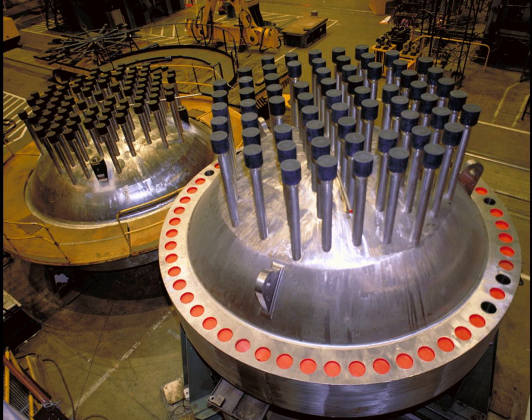The high-temperature water coolant with boric acid dissolved in it is corrosive to carbon steel but not stainless steel. This can cause radioactive corrosion products to circulate in the primary coolant loop, limiting the lifetime of the reactor. The systems that filter out the corrosion products and adjust the boric acid concentration add significantly to the overall cost of the reactor and to radiation exposure. In one instance, this resulted in severe corrosion to control rod drive mechanisms when the boric acid solution leaked through the seal between the mechanism and the primary system. Natural uranium is only 0.7% uranium-235, the isotope necessary for thermal reactors, making it necessary to enrich the uranium fuel, which significantly increases the costs of fuel production.